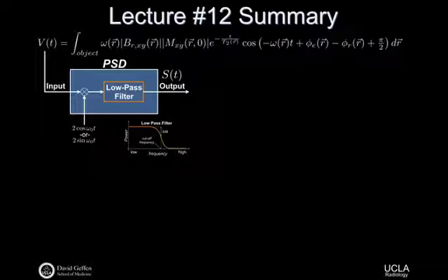Omega depends on what? Spatial position, right? And omega is the frequency, right? The precessional frequency. So this was a precessional frequency at each spatial location, right? How can we get the precessional frequency to be different at different locations? Apply a gradient. So this term here, we'll link it up more today, is actually really important because this is where the spatial frequency information comes from. The spatial encoding is actually coming from it.